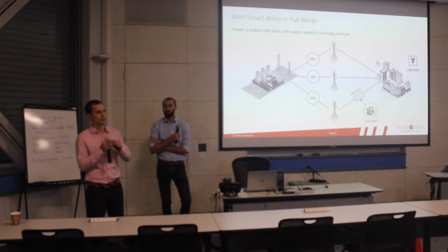On the question of how this could work with seams: if you look at the different regions in Europe, or the US, ERCOT in Texas essentially is its own grid with its own frequency not linked to the other US grids. But they still want to share power back and forth, so they'll have an interconnection. That interconnection converts power to DC and back to AC, so power transferring into Texas becomes synchronized with the ERCOT grid frequency, or if it's going out, it has to be changed so you're not injecting real power that's unsynchronized with that grid. So those seams use power electronics similar to what we do, but it's not necessarily a power flow technology.